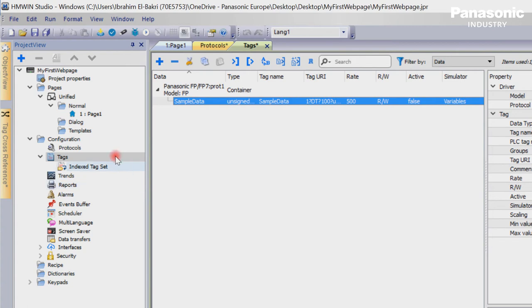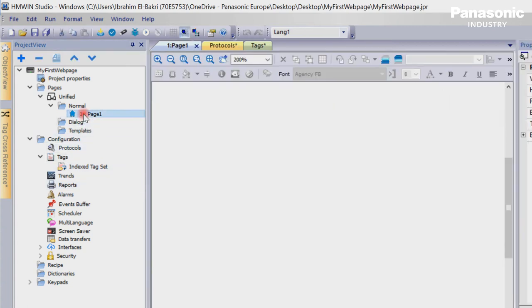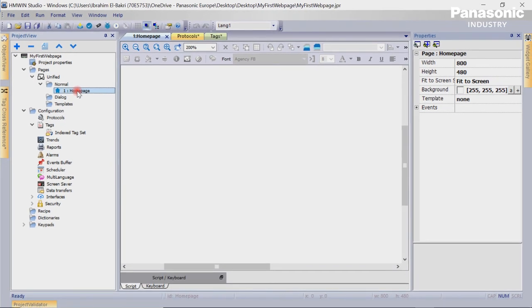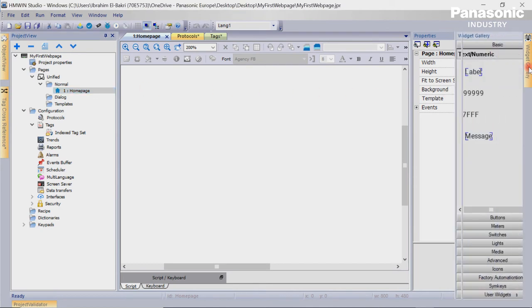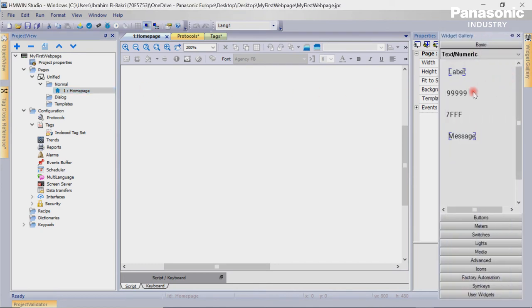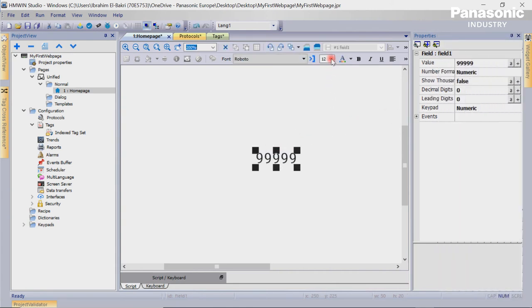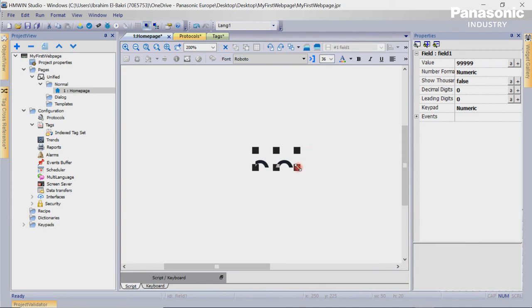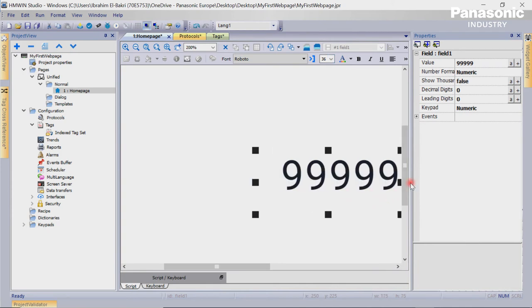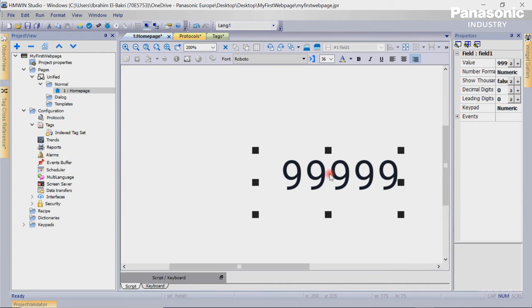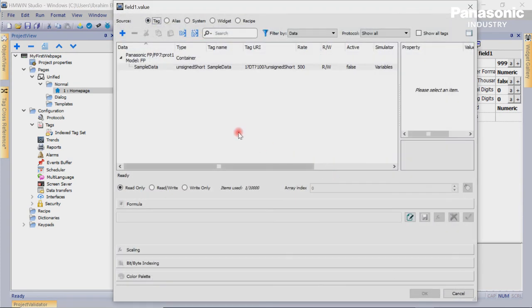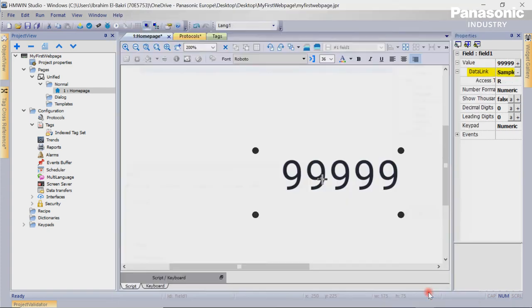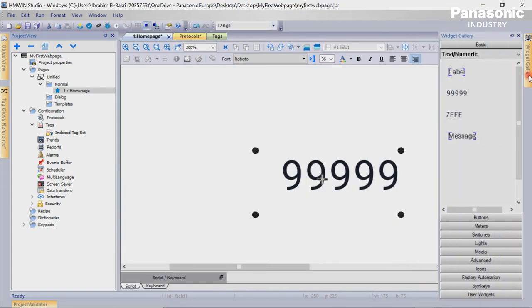We then go to page 1. Let's rename page 1 to HomePage. We open the widget menu at the right side of HMWIN Studio and select the according widget for displaying numeric values. We double-click on the element and select the PLC tag we defined before. We then press OK. We add a label and rename it to SampleData.